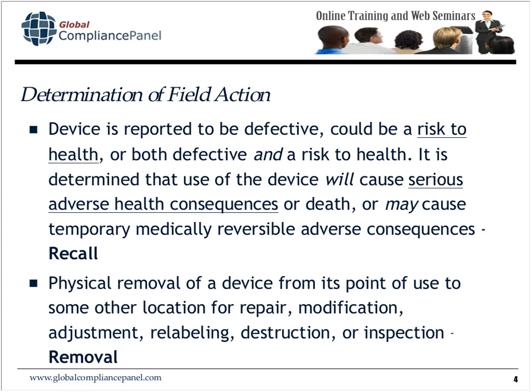When it comes to determination of field action, the characteristics of the need for field action are what's going to push you in the direction of what type of field action to take. If you have a certain device and it's reported to be defective, and it could be a risk to health, that's going to be a recall. However, if it's been defective and a risk to health, it's going to be a recall also. So in one situation, it's defective, maybe it could be a risk to health, maybe not, recall. Defective and absolutely risk to health, recall also.